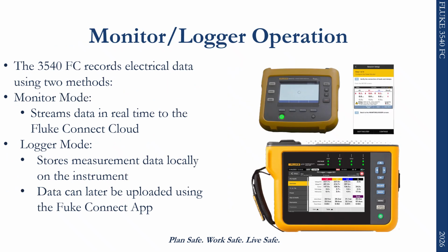The Fluke 3540 FC can record electrical data using 2 operating modes. In monitor mode, the device streams electrical data in real time to the Fluke Connect cloud so it can be viewed remotely. In logger mode, the device stores measurement data locally on the instrument. That data can later be uploaded and reviewed using the Fluke Connect application.